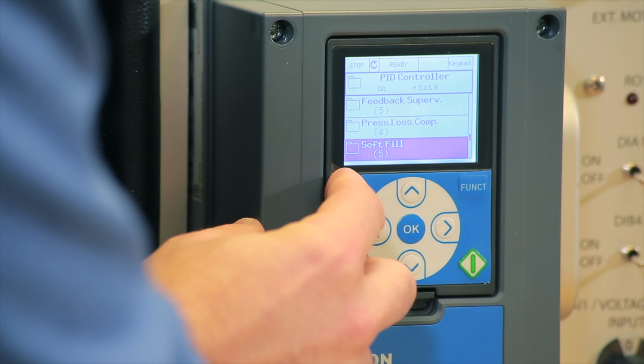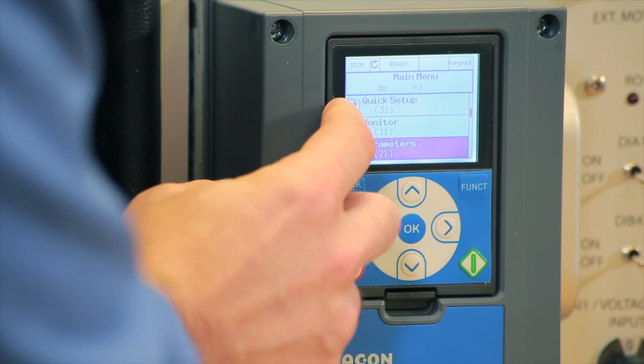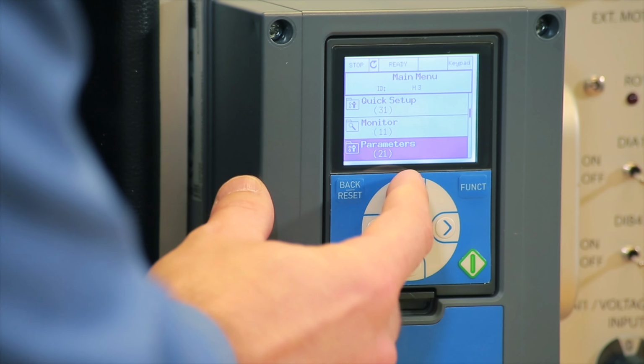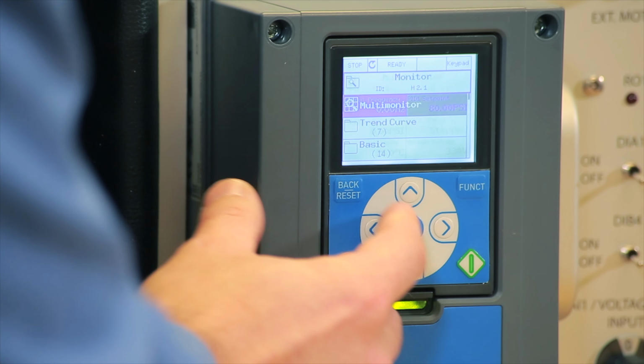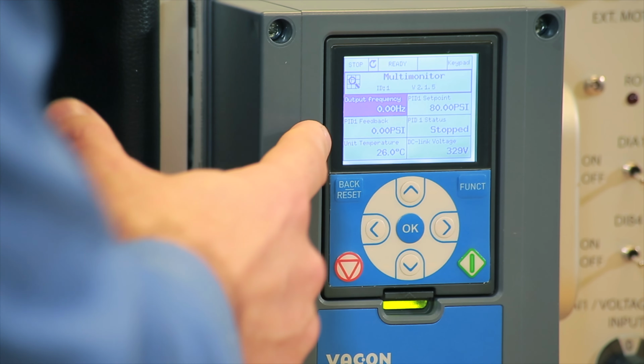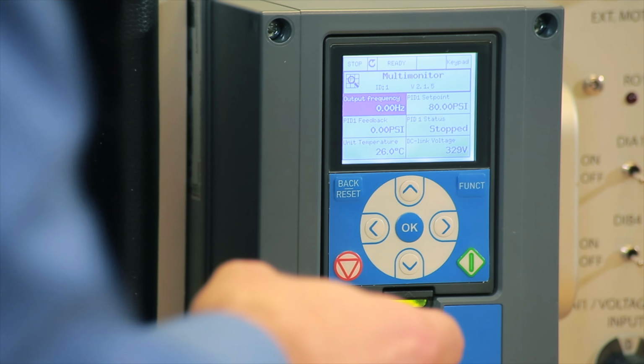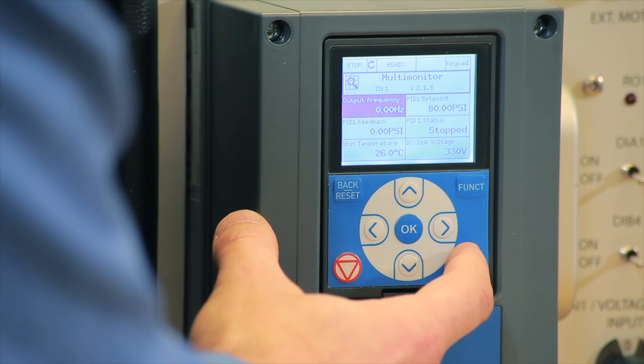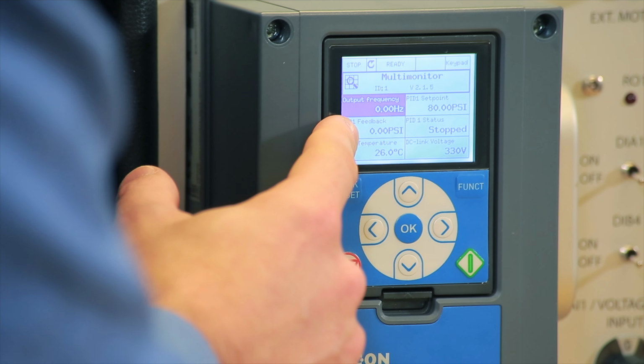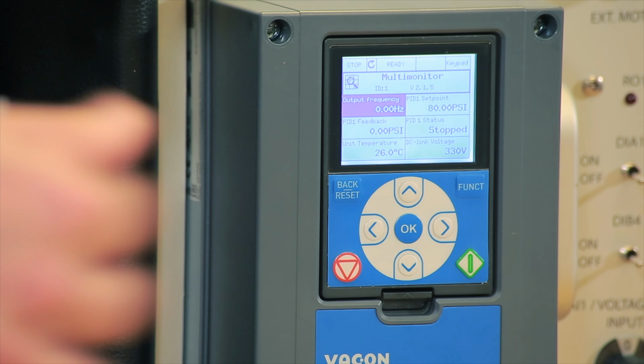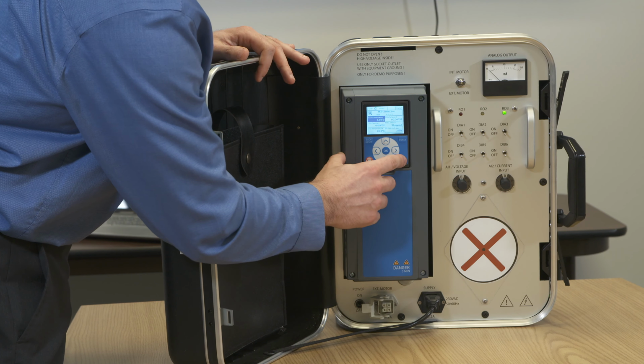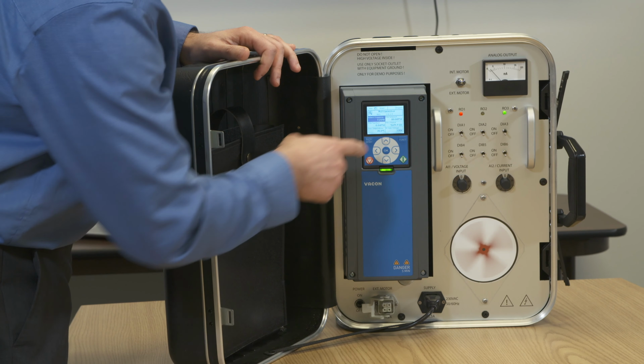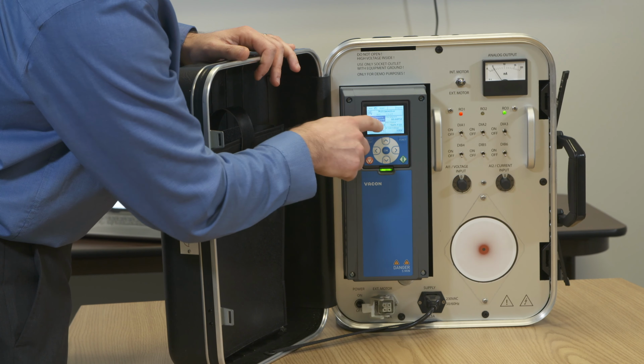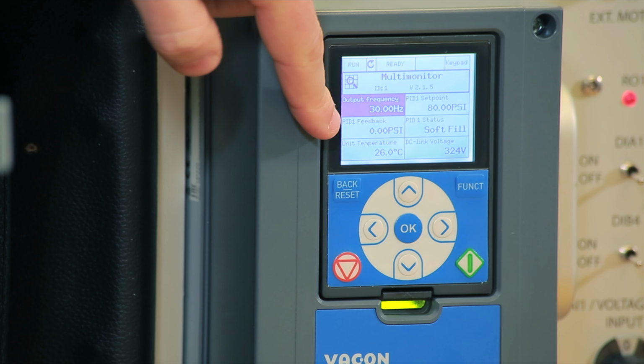We're going to go back all the way until we get to the main menu, and then we're going to go back to multi-monitor. This is where we're going to monitor what's happening with the drive. So let's run it, and we have PID feedback 0, so that means the pipes are empty. Let's click on run. The drive says soft fill. So the drive is running right now at 30 hertz until we see 35 psi.